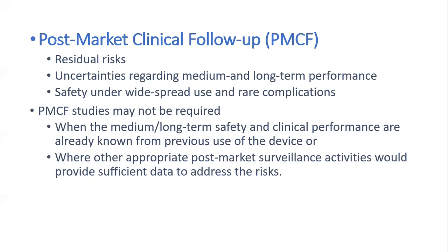Where other post-market surveillance activities would provide sufficient data to address the risk, PMS activities also give you inputs for the risk. So this is for low risk, but for a high-risk device, you have to perform a PMCF study or a PMCF trial.